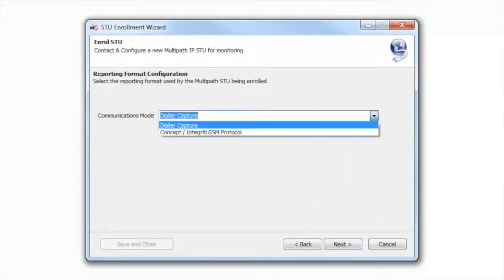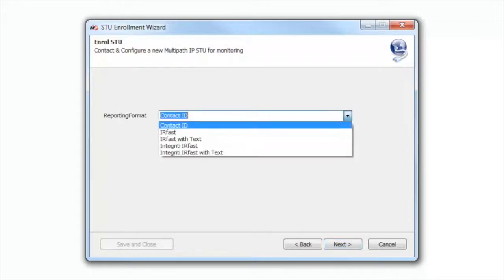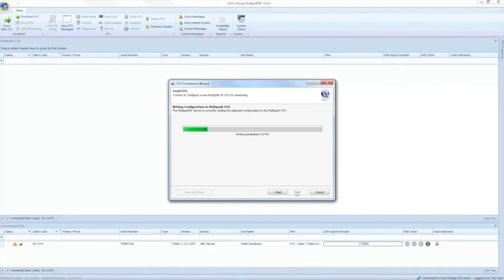Select the communications mode. For this installation, we are using dialer capture. Select the reporting format. We are using Contact ID for this installation. The T4000 is also capable of reporting IR Fast with preview text to the central station. The system is now programming the T4000. Once complete, click the finish button to finalize enrollment.